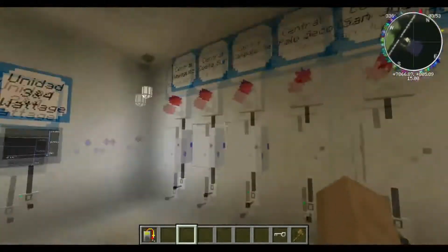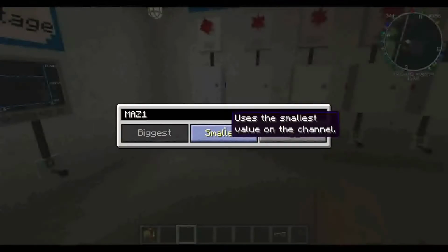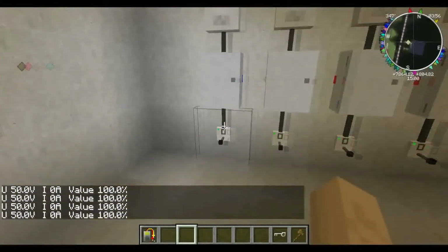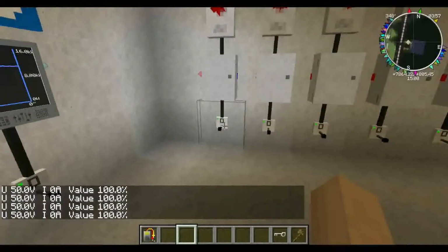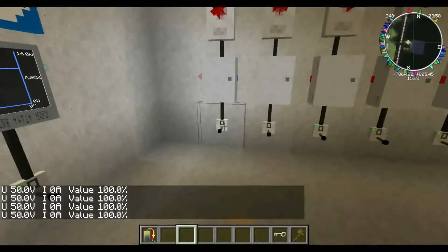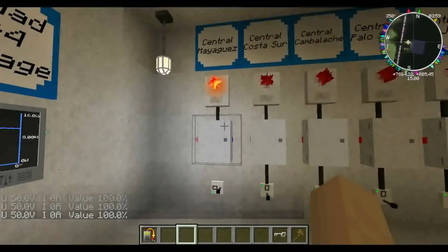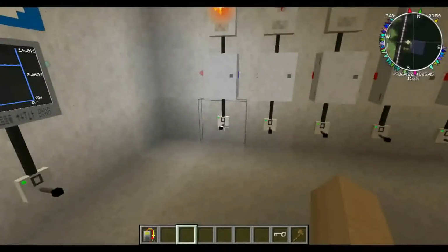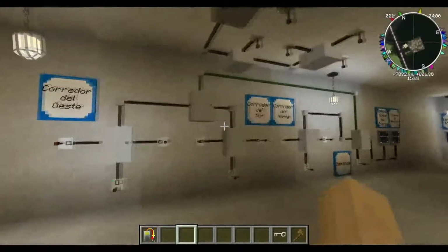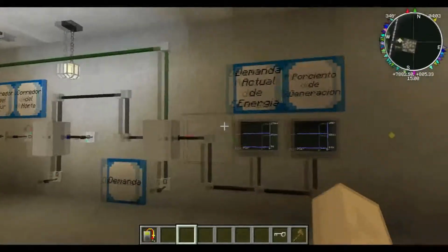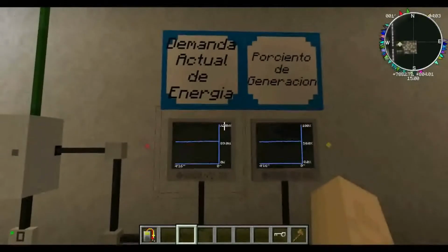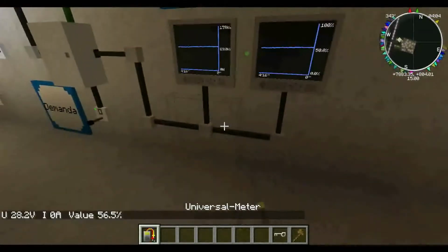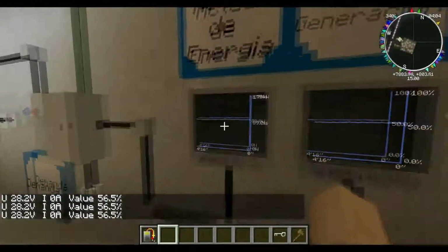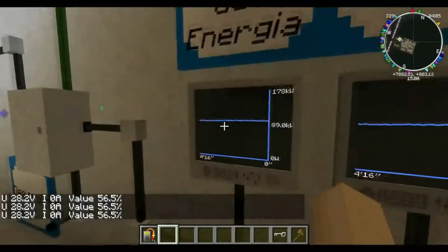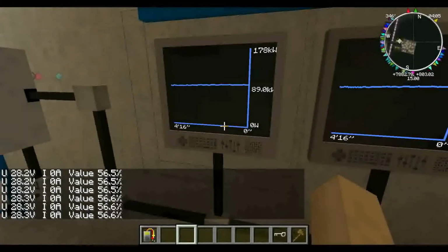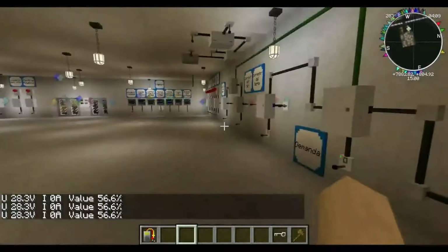You can see right here, this indicates when you lose the signal. Let's say right now it's 50, it means the steam turbines are generating. If they stop generating, an alarm will sound indicating that the power plant has shut off. Right here we have calculation processors for calculating the actual energy demand and the percentage of generation. The maximum capacity of this system is 178 kilowatts, and right now it is consuming somewhere around 93 kilowatts.